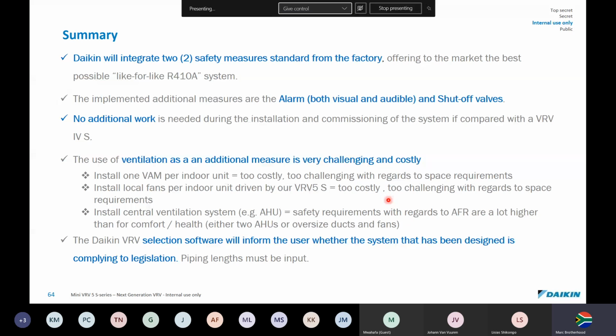The safety requirements with regards to the AFR are a lot higher than for comfort cooling. The good thing is the Daikin VRV selection software, when you design it on VRV Express, will inform the user whether the system has been designed to comply with legislation. Now, the only way to comply with legislation, you have to put the pipe lengths in. And I don't know if the software is going to allow you to just do a design with R32 if you don't put the pipe lengths in. They want to know the pipe lengths to let you know if there's too much refrigerant in the system to leak into the smallest room. That is the risk.